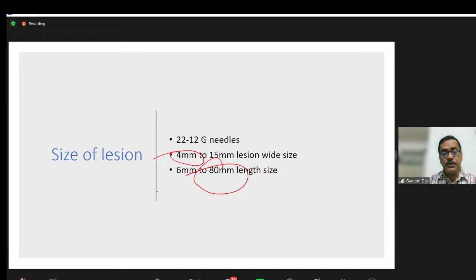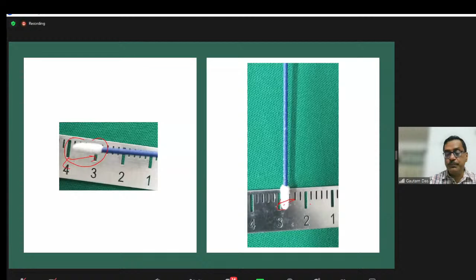You see, this is the ice ball - here the ice ball is very small, the length is approximately 8 millimeters, width approximately 3-4 millimeters. Whereas if you see this one, here the length of the lesion is more than 80 millimeters. So we have the flexibility that by using the cryo probe - not the machine setting, machine setting is different - if you wish to have a larger size lesion, you have to use a different probe, not the same probe.